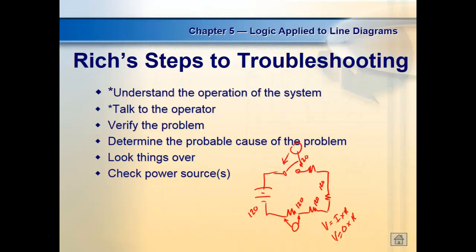Normally when we troubleshoot and check voltage levels, we move from right to left — we take one of our leads and connect it to L2, then start moving from L2 toward L1 until we see a voltage. As soon as we see voltage, we know where the problem is. We don't like to probe with two meter leads inside a live circuit — why? You've got two hands up there, and probably one of the most dangerous paths is hand to hand.